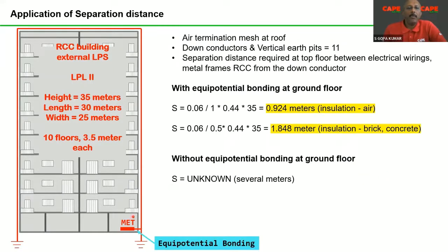And this is with equipotential bonding at the bottom of the building. Now, if you don't have the equipotential bonding at the bottom of the building, the separation distance is really unknown. It may be several meters. Now, the question is, when you do lightning protection, are you making this equipotential bonding? You are making an exposed lightning protection system. Are you making the equipotential bonding?